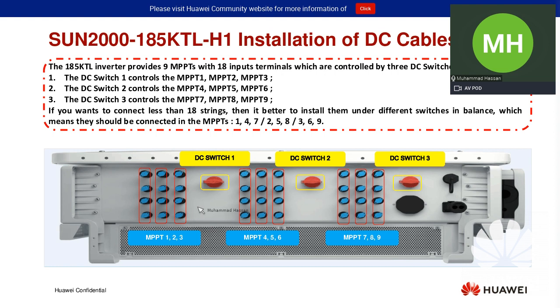It's safer: if you need to work on any strings, you just switch off the DC switch related to that MPPT, and you can work safely on that particular part of the inverter. But I always recommend disconnecting all the DC switches before working on any input of the inverter, due to health and safety issues. But if you want to work on any part of the inverter, you can switch off the relevant DC switch and work safely on that part. Our recommendation is that when you are disconnecting or plugging in any strings, always make sure the inverter is totally isolated from the DC side and from the AC side, so that you can work safely on the inverter.